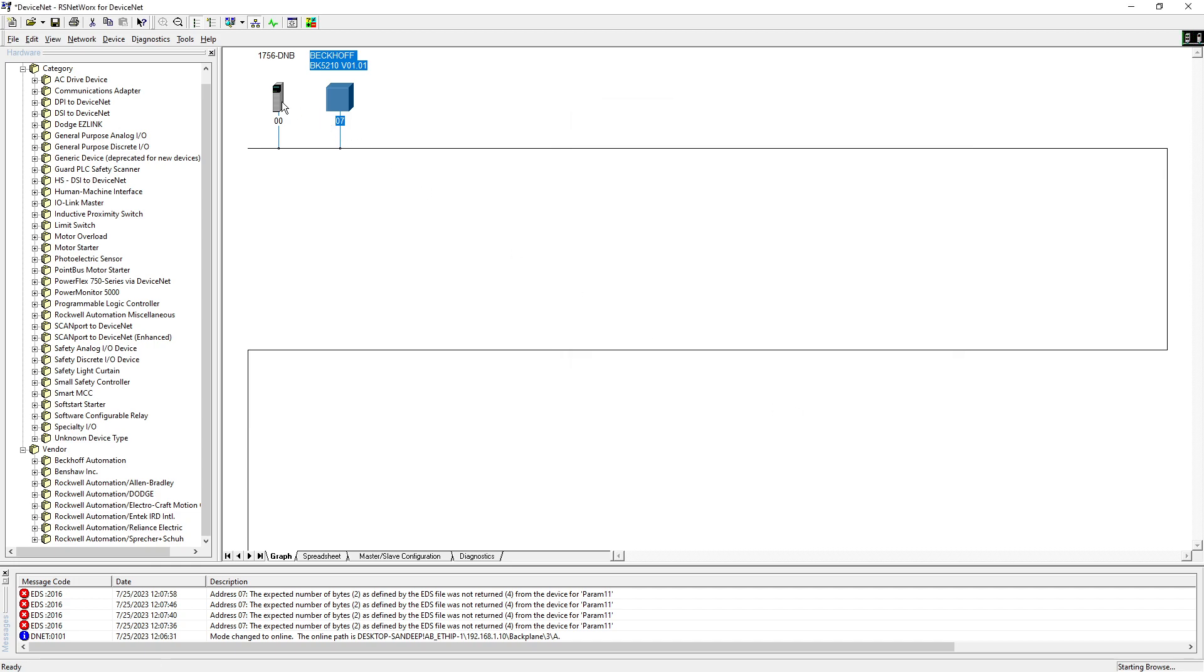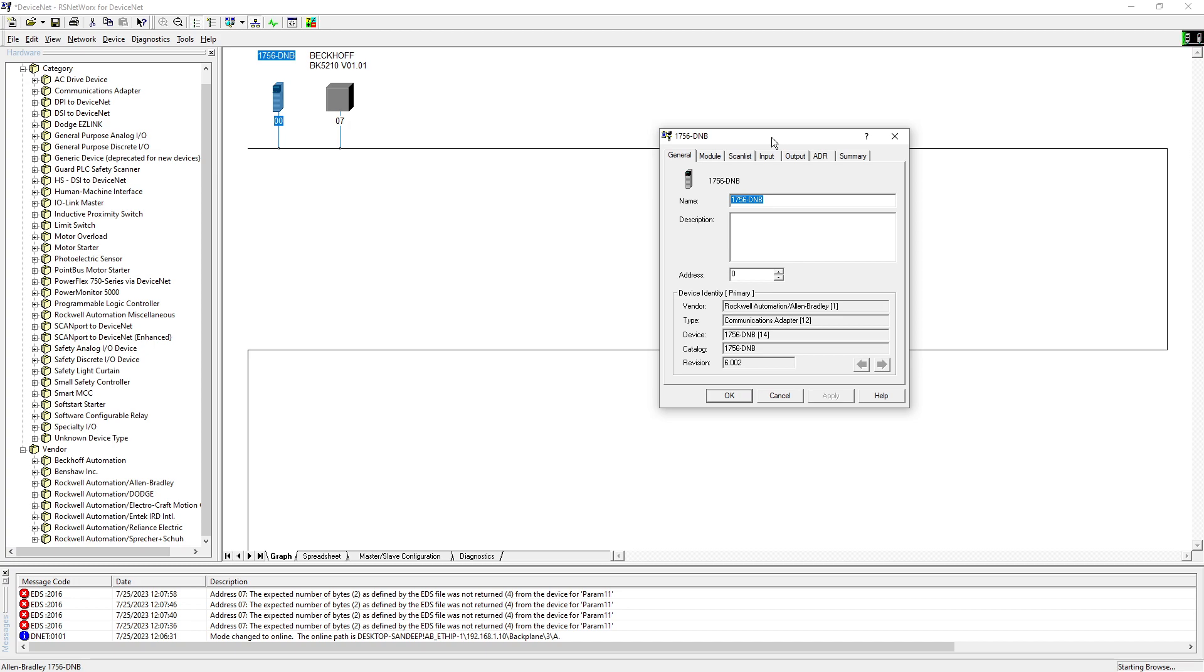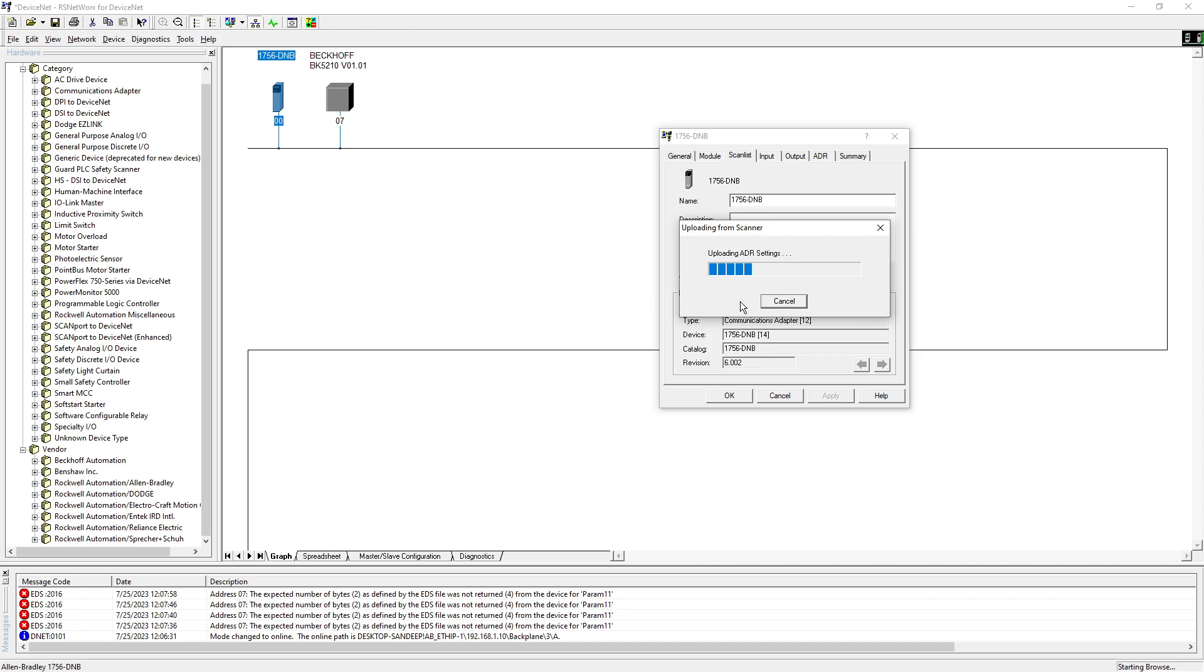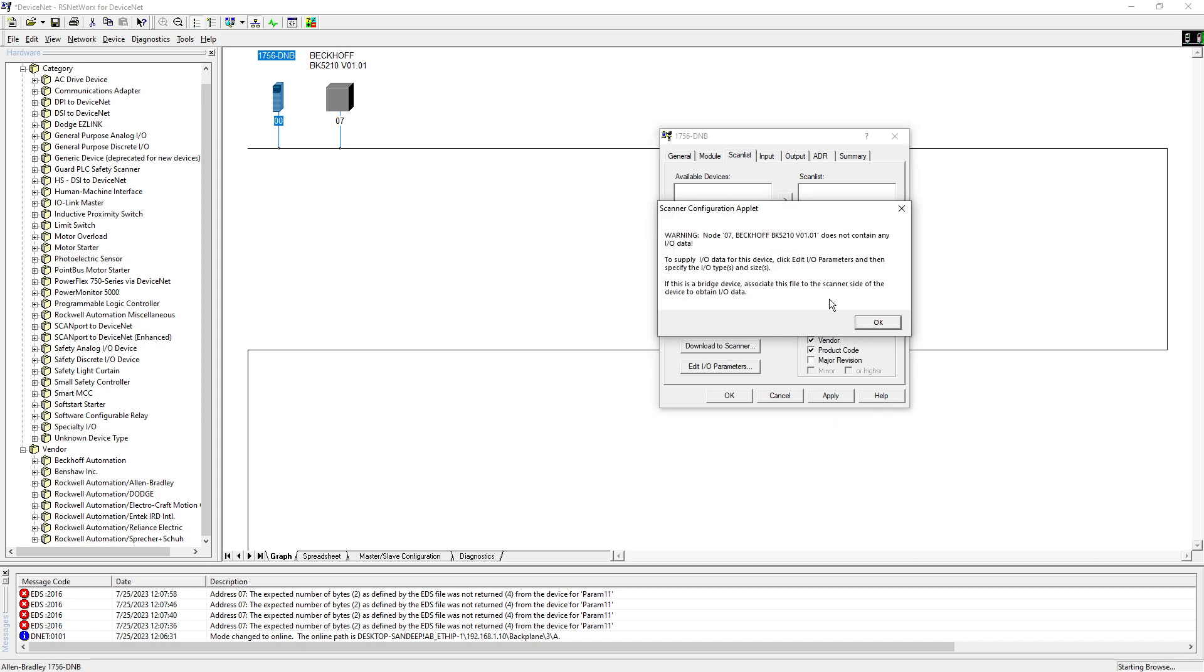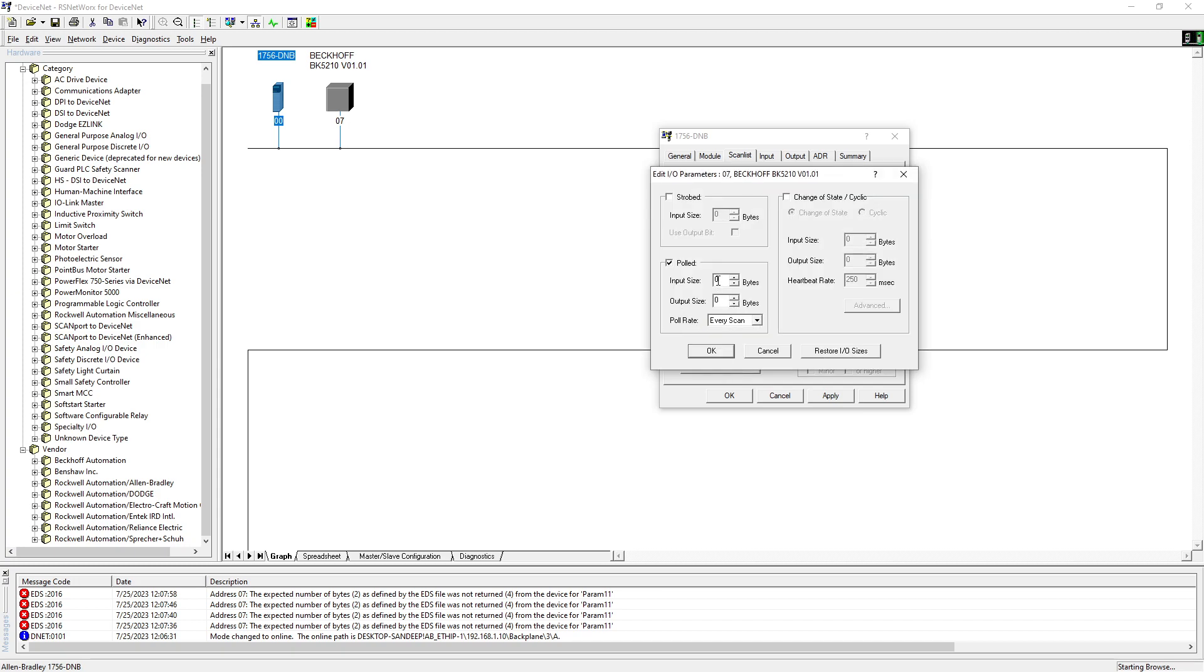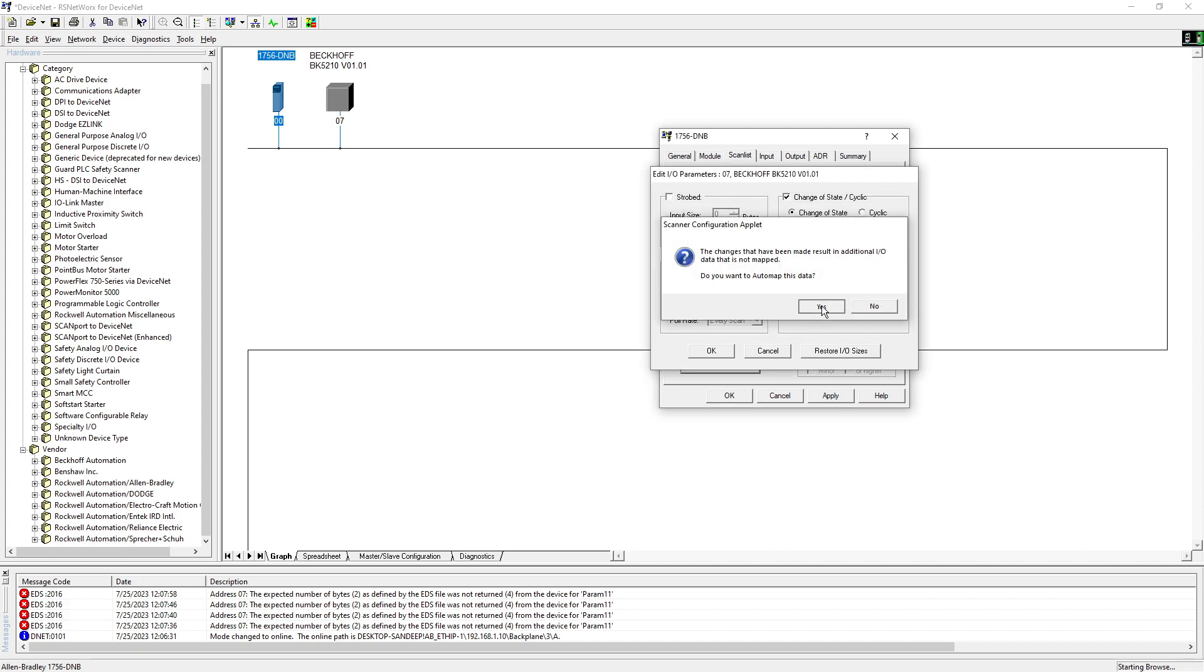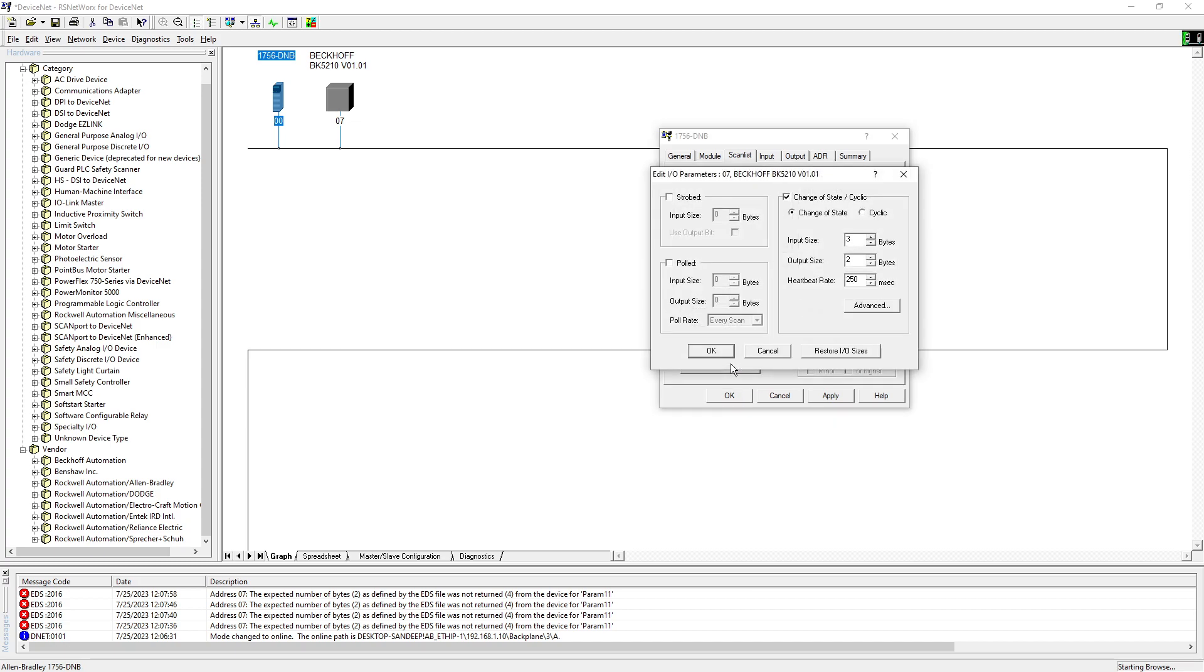And I will hit okay. Now I go into my DNB, I will go to scan list, I will upload. I will just remove that whatever that is, so I will click on Beckhoff. I will put it in the scan list. Now I go edit parameters, so our COS input size was three bytes and output size was two bytes. Hit okay, yes, yes. We will double check that if it's there or not, yep.